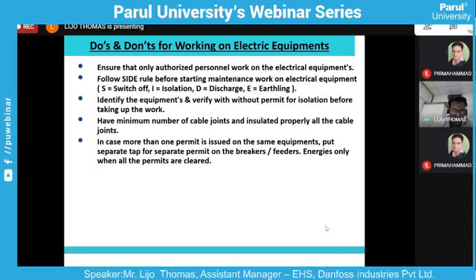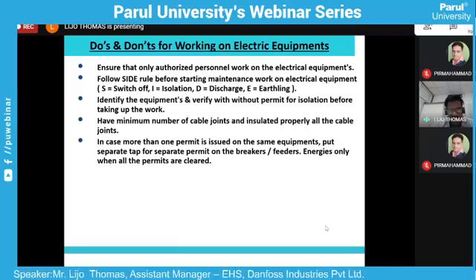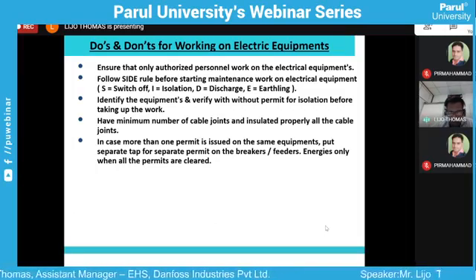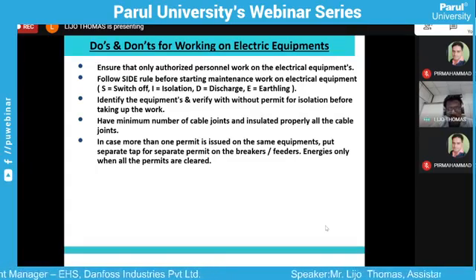In case more than one permit is issued on the same equipment, put a separate tag for each separate permit on the breakers. You energize only when all the permits are clear. As I already mentioned, start any work only after your work permit is properly cleared.